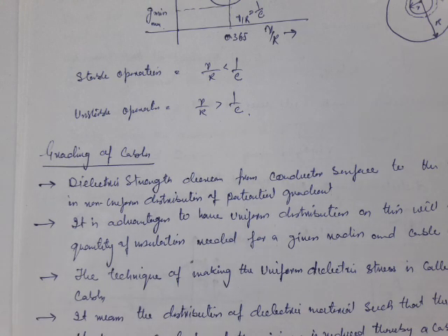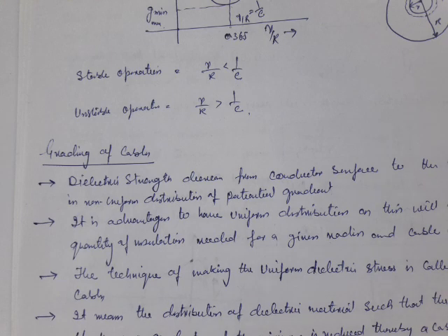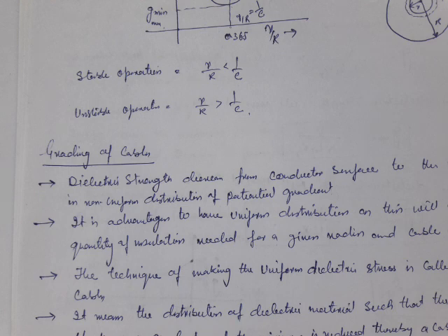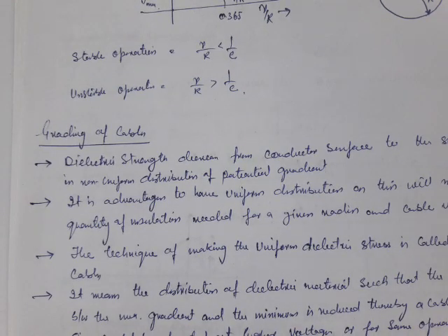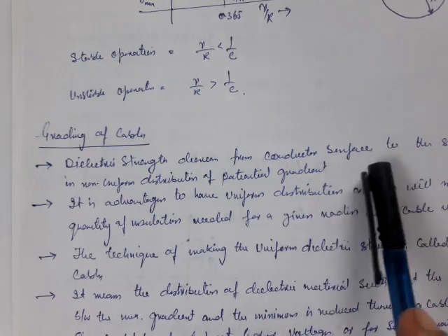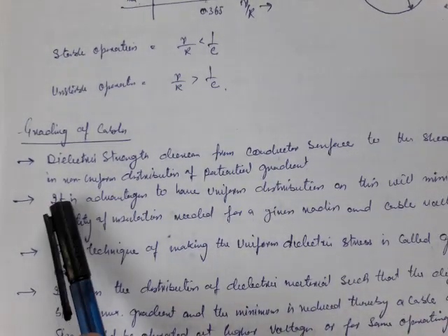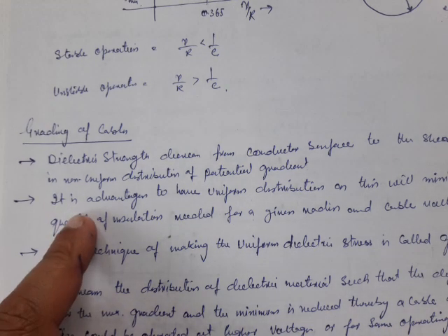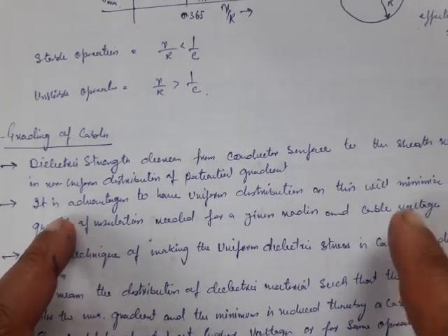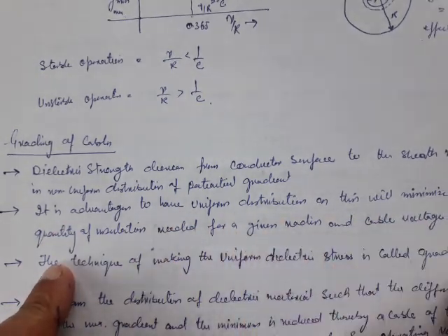Now we come to the grading of cables. In this case, we want the potential distribution along the dielectric to remain within certain limits so the dielectric does not get damaged. Dielectric stress decreases from the conductor surface to the sheath, resulting in non-uniform distribution of potential. It is advantageous to have uniform distribution, as this minimizes the quantity of insulation needed for a given cable radius and voltage.